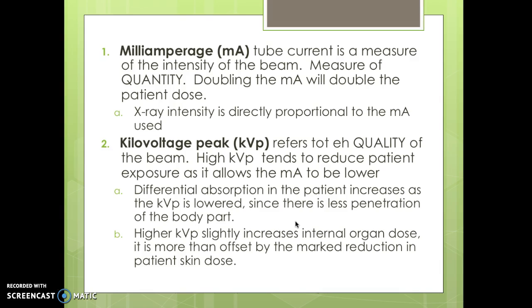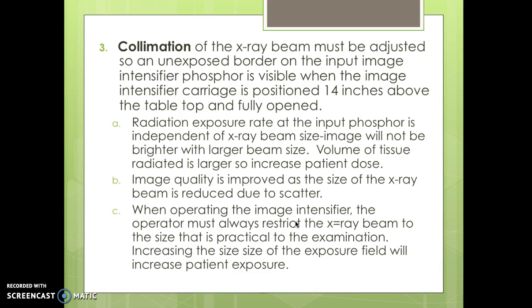With kilovolts peak (kVp), we're talking about the quality of the beam. High kVp tends to reduce patient exposure because it lowers the mA — as kVp goes up, mA goes down. Differential absorption in the patient increases as kVp is lowered since there's less penetration. Higher kVp slightly increases internal organ dose, but this is more than offset by the marked reduction in the patient's skin dose.